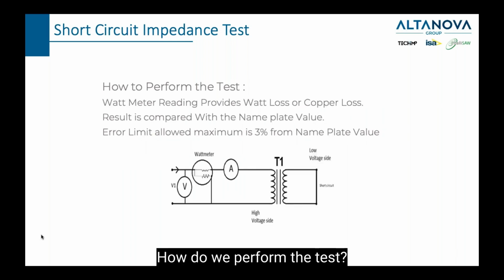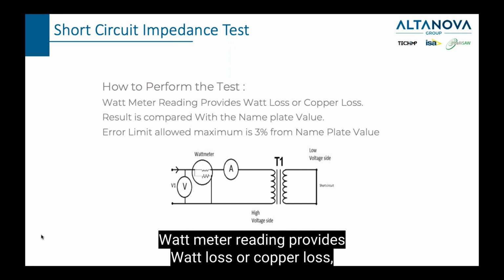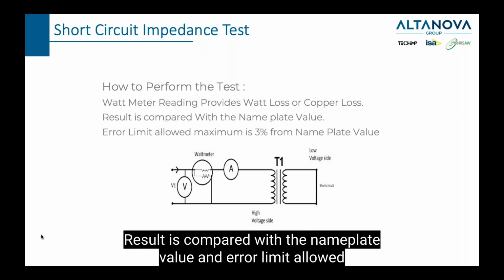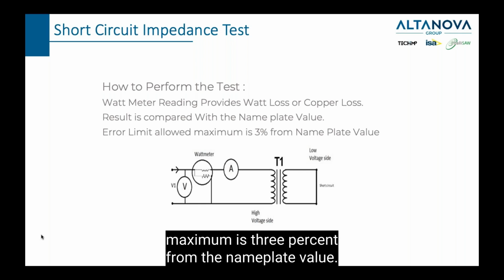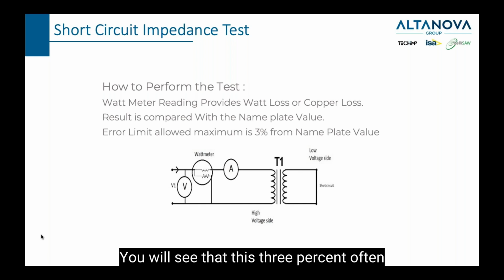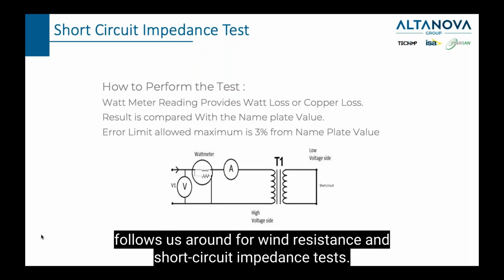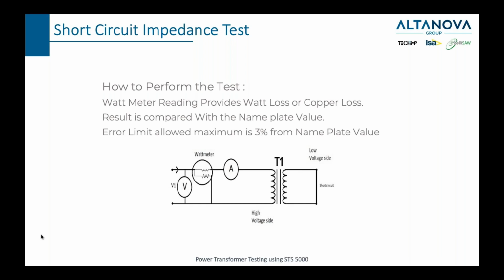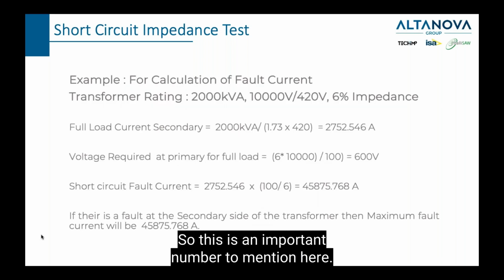How do we perform the test? Watt meter reading provides watt loss or copper loss, so what we're losing in the copper. The result is compared with the nameplate value, and the maximum allowed error limit is 3% from the nameplate value. You will see that this 3% often follows us around, not only for winding resistance and short circuit impedance test. So this is an important number to mention here.